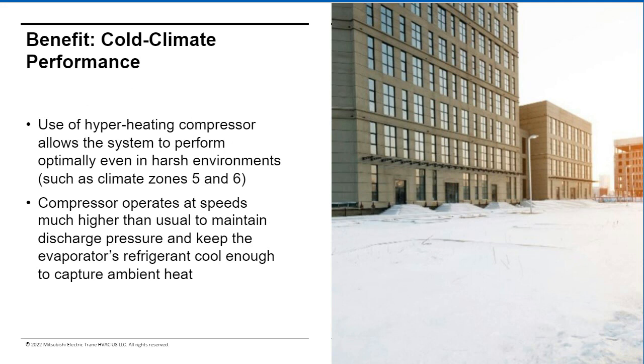Some CO2-based heat pump water heater systems utilize specialized compressors that include flash injection, which is an auxiliary cooling circuit that allows the compressor to achieve higher compressor speeds at low ambient conditions without risking damage to the system, thereby achieving higher lift and more BTUs per hour than other inverter scroll compressor-based systems. Some manufacturers can achieve 100% of nameplate heating capacity at 36 degrees Fahrenheit ambient, and 50% of nameplate heating capacity at negative 13 degrees outdoor ambient conditions.